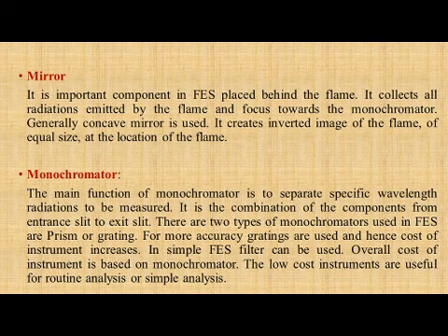The focal point of the mirror is adjusted to the aperture of the entrance slit, and all the radiations are collected here. Generally, a concave mirror is used for that purpose. It creates an inverted image of the flame of equal size at the location of the flame, and the main function of this mirror is to collect all the radiations emitted by the flame for a good measurement.